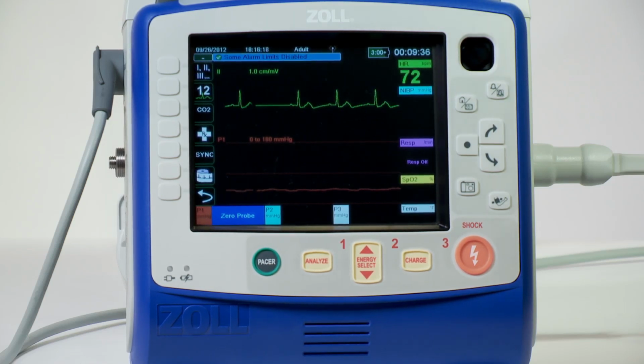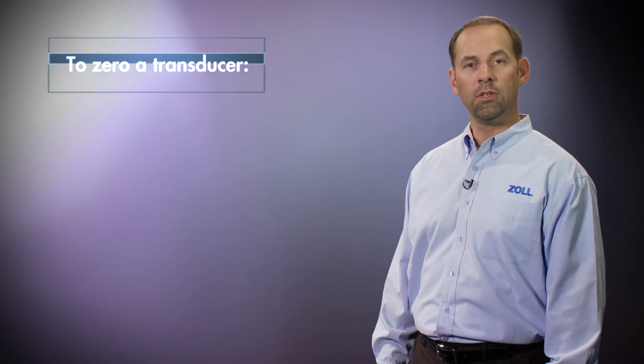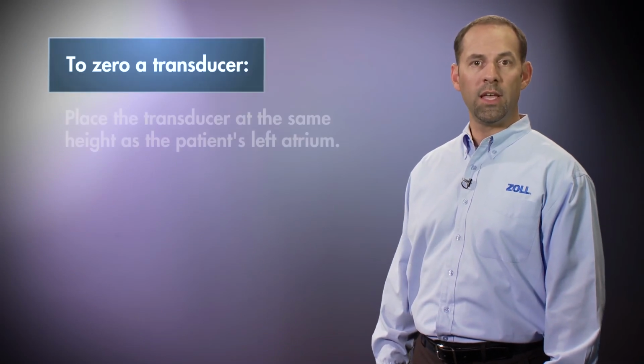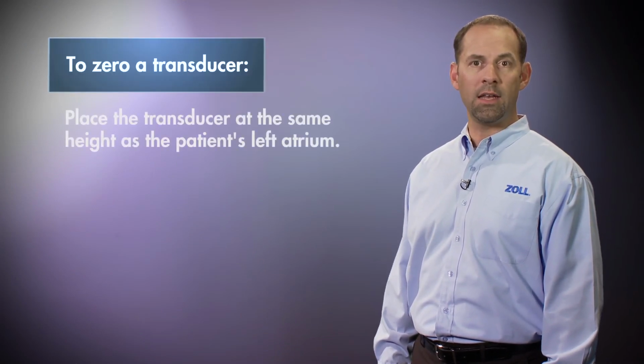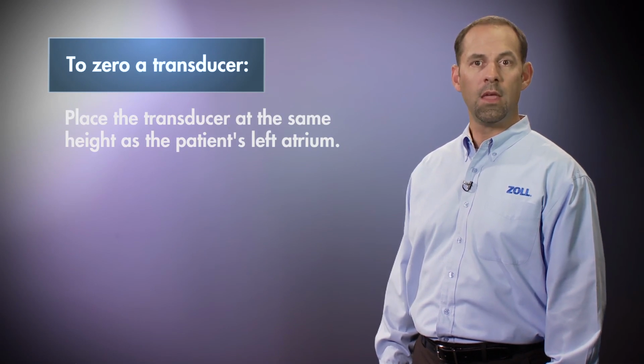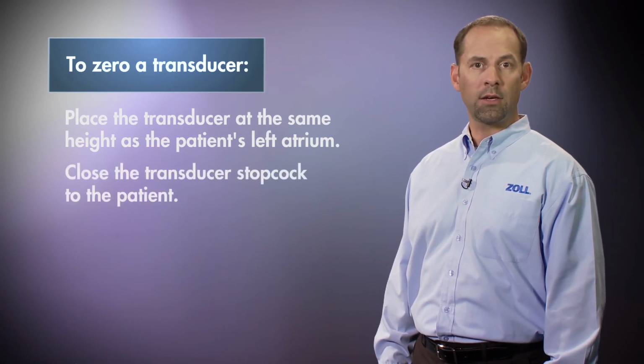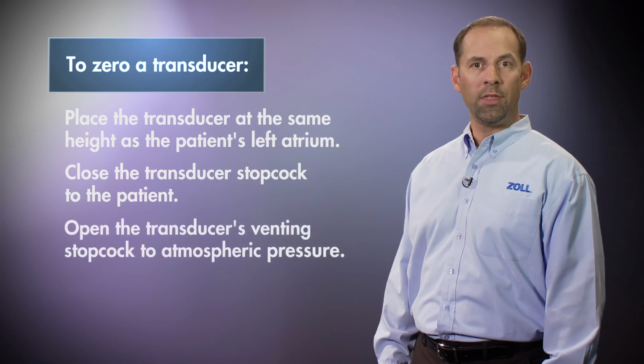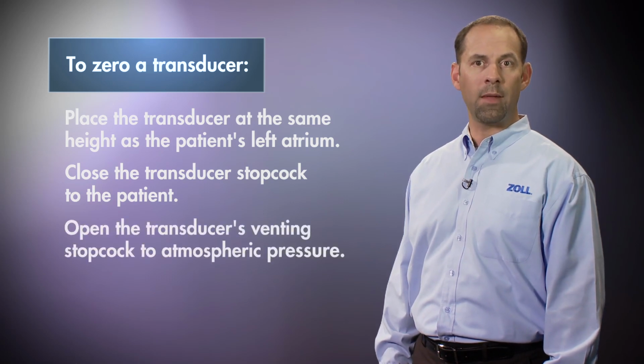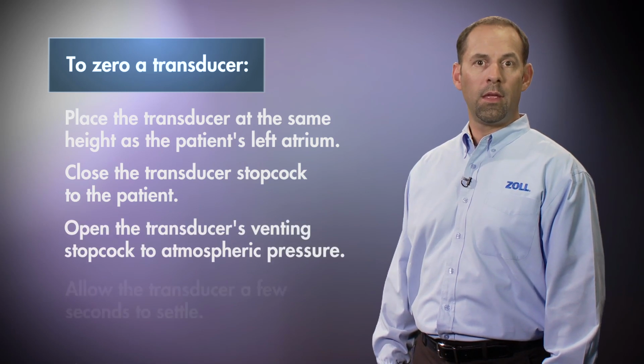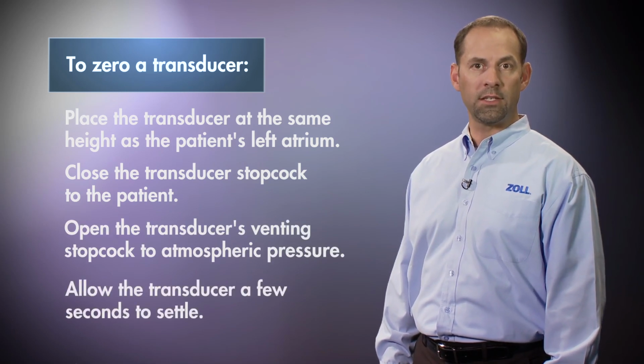If you change or disconnect a transducer, you must zero the new transducer before use. If you move the transducer to a different monitor, you must zero the transducer again, even if you have already done so on another unit. To zero a transducer, place the transducer at the same height as the patient's left atrium. Close the transducer's stopcock to the patient. Open the transducer's venting stopcock to atmospheric pressure. Allow the transducer a few seconds to settle.